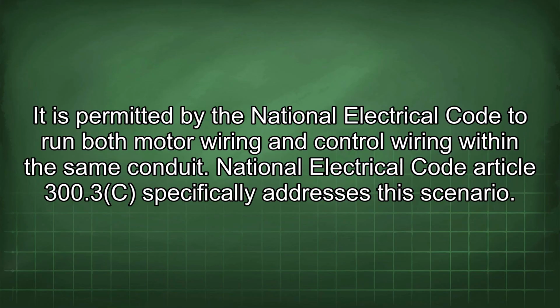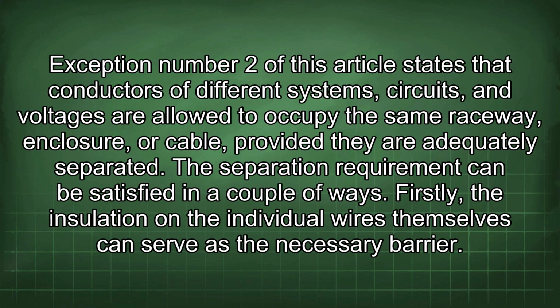It is permitted by the National Electrical Code to run both motor wiring and control wiring within the same conduit. National Electrical Code Article 300.3(C) specifically addresses this scenario. Exception number 2 of this article states that conductors of different systems, circuits, and voltages are allowed to occupy the same raceway, enclosure, or cable, provided they are adequately separated.